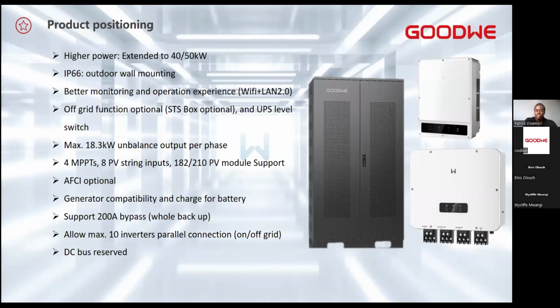The ET 40 or 50 along with the STS allows you to integrate your system with generators. So if you want to run your system off-grid with 3 levels of priority, first priority being the PV, second priority being the battery, third priority being the generator, yes, the system allows that. You can work with the grid and ensure zero export. Once the grid fails, in UPS level less than 10 milliseconds, the inverters will be discharging power from the battery banks. And if the battery banks reach a certain SOC or depth of discharge, the inverter can send a signal to the generator for startup, and the system can work with the generator as well, thus utilizing your PV and minimizing your fuel consumption from the generator.